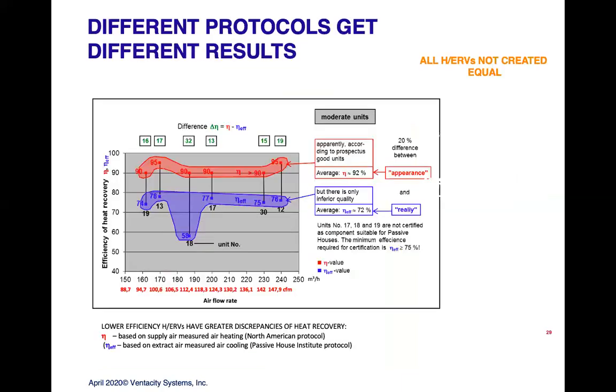As far as measuring goes, very quickly, the difference between AHRI and HVI and Passive House is that North America measures efficiency by the outgoing airstream. They measure the temperature leaving. If it's 70 degrees inside, 30 degrees outside, and you're supplying air at 66 degrees, there's a 40-degree difference. If you're bringing in air at 66 degrees, then that's a 4-degree loss, call it. So that's considered 90%. That's 4 out of 40. That's 90% efficient. The problem is there are a lot of things that influence that incoming airstream.